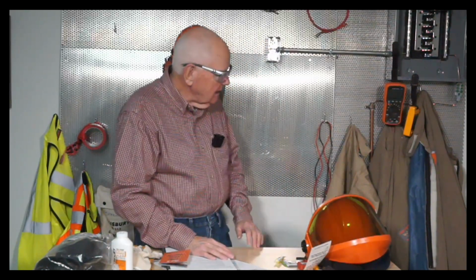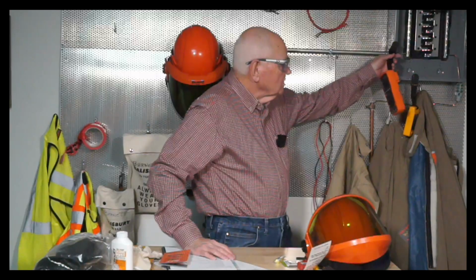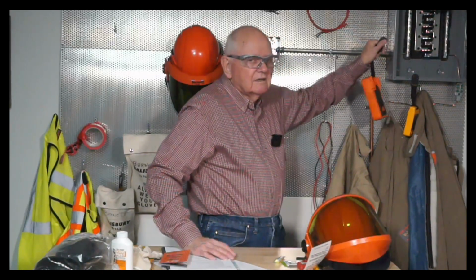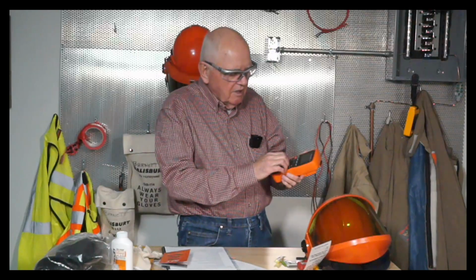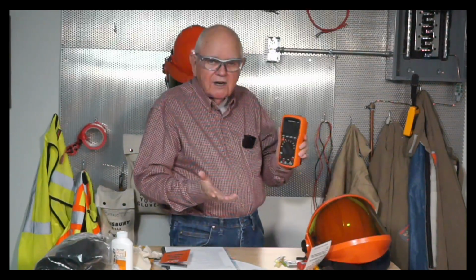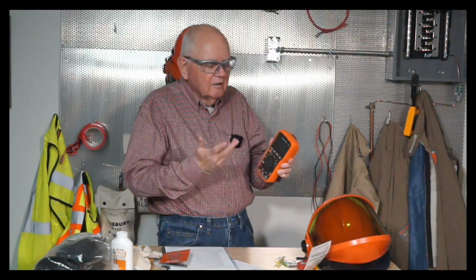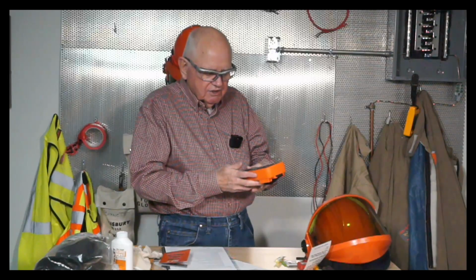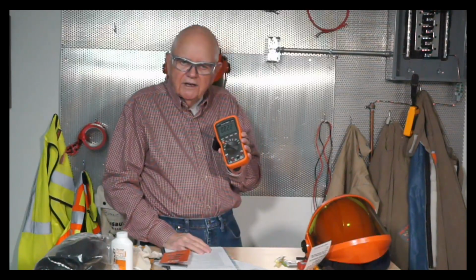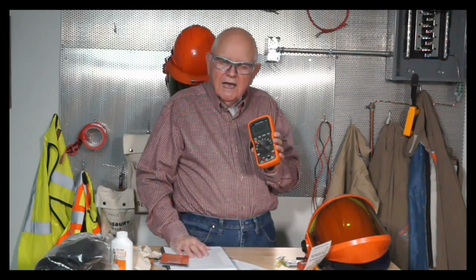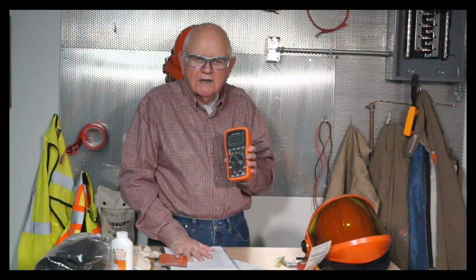Something else we may need, depending on what we're doing, of course, is our test equipment. So we may need a multimeter. The things that I want to do is I want to check my multimeter, turn it on, make sure I don't get the low battery on it, comes on. Physically, it's in good shape. I check the category rating on it. The more category I have, the more protection I have. Category 1 is fine for some bench work right here.